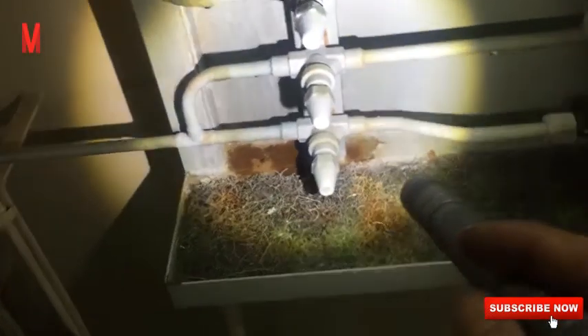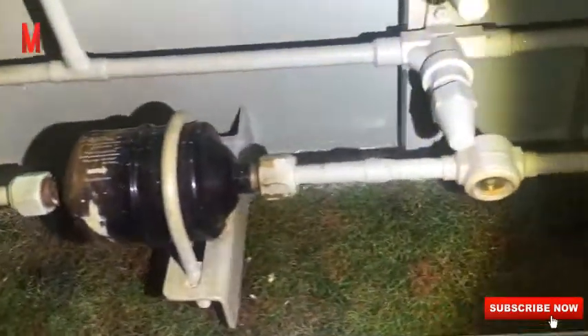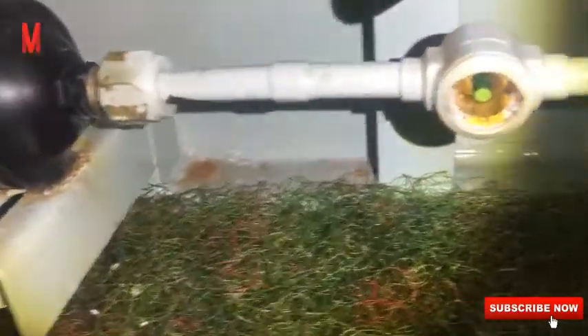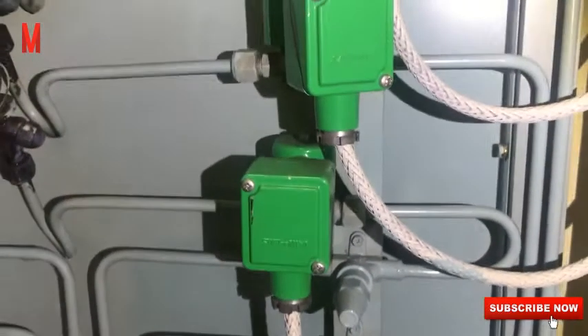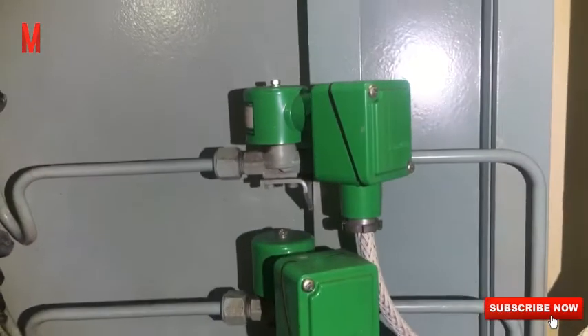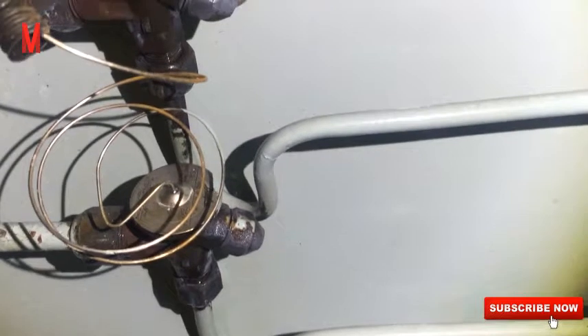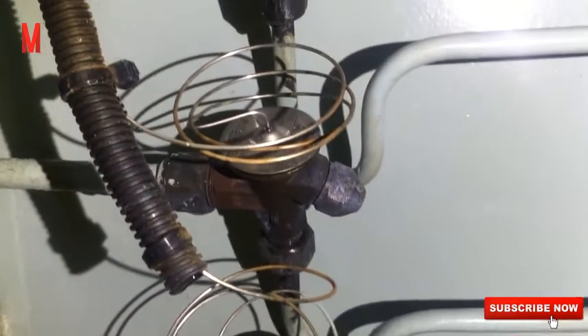And we have the safety valve. This safety valve, if the high pressure switch does not work for some reason, this valve, which is installed on the condenser, will work and let the refrigerant escape out of the system. This prevents the pressure from rising abnormally in the system. So never close this main safety stop valve, because this safety stop valve must be piped so as to let the refrigerant escape out of the ship to prevent the overpressure.